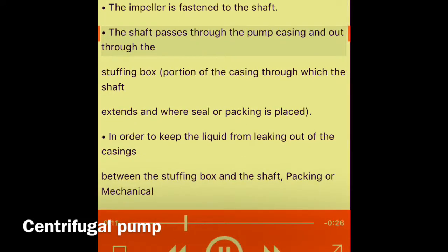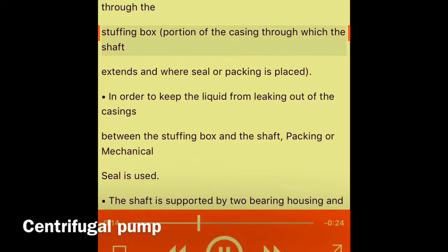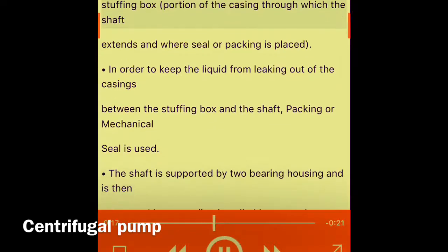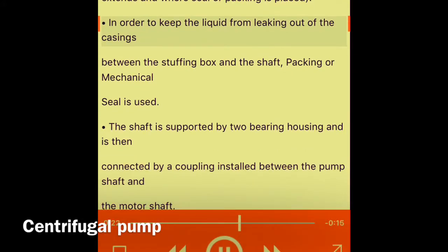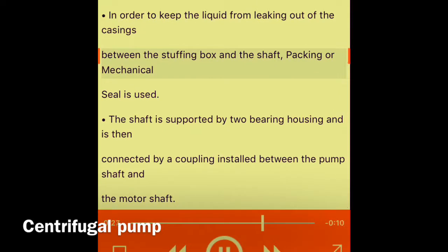The portion of the casing through which the shaft extends and where seal or packing is placed, in order to keep the liquid from leaking out of the casings between the stuffing box and the shaft, packing or mechanical seal is used. The shaft is supported by two bearing housings and is then connected by a coupling installed between the pump shaft and the motor shaft.